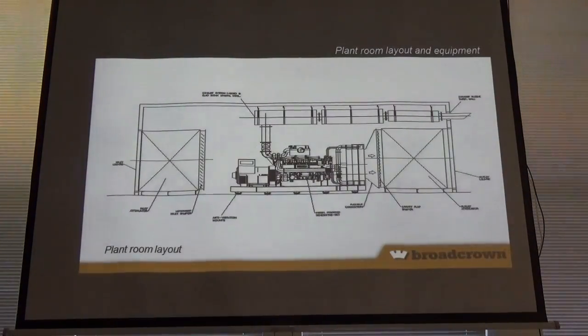However, these points here are the most sensitive. Put it this way, if your set's right in the middle of the building, and you've got literally 20 metres away from that unit, they're saying it needs to be 55, maybe at these measuring points here. If that set is sitting right in the middle of the building, and you've got a 20 metre distance, you've got a natural loss over that distance anyway. So over about 20 metres, you've probably got an 18 to 20 dBA drop. So you add that back, that's 75 dBA at one metre. So you can extrapolate, and then you can actually have a unit that's taking a smaller footprint.